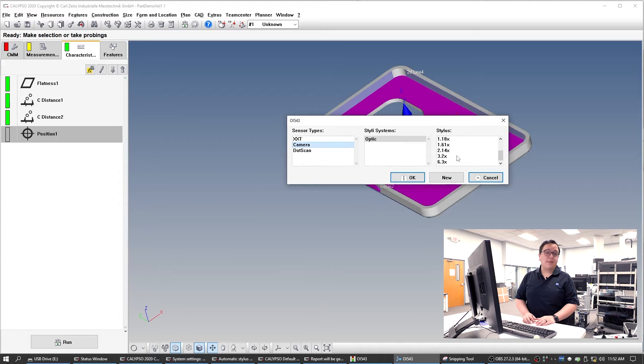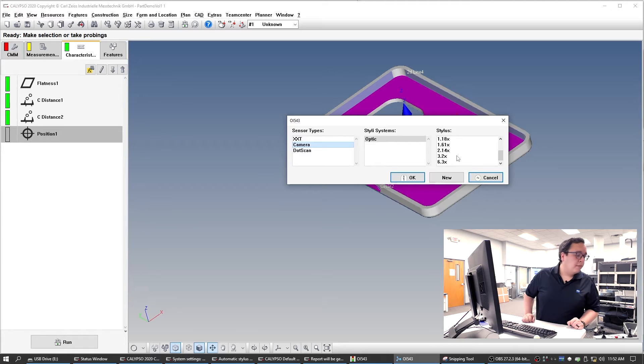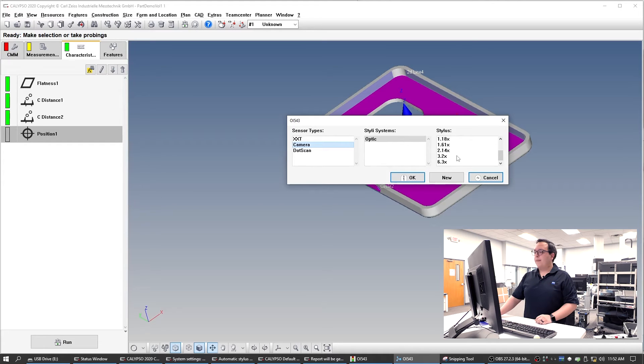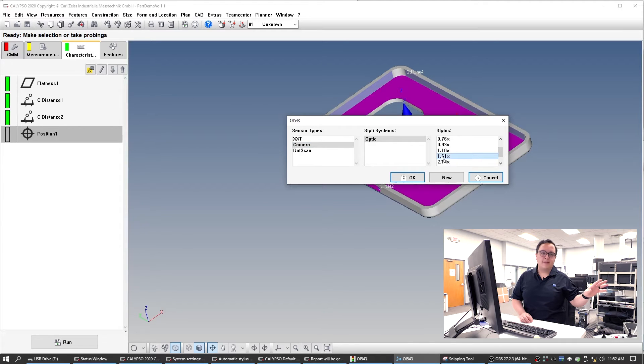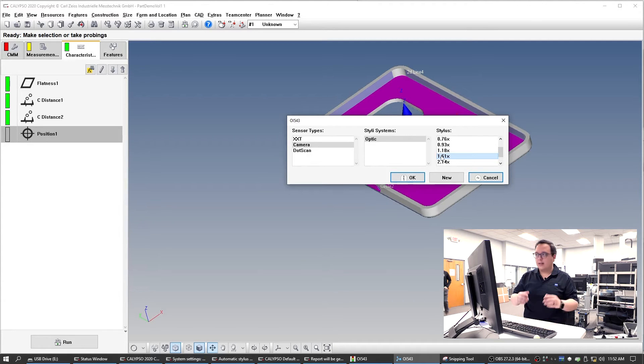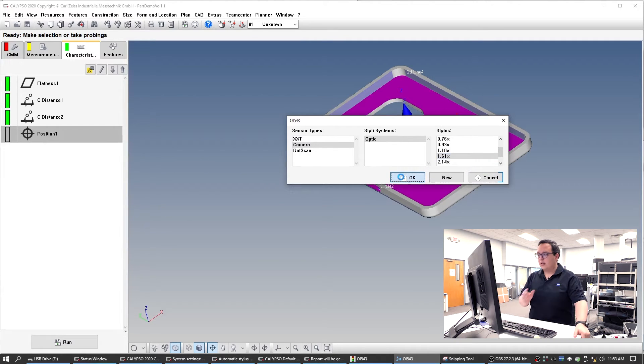We can turn on the camera by going to the little hand — this is the manual input for the stylus camera. We have ten different magnifications to pick from. Which one do we want to use? It depends on the tolerance that we're going to put on this characteristic. If it's really small, you want to measure with the largest magnification possible. If it's big tolerance, you want to make sure you can find your part. Here I will use the 161. The 161 is really special for the Oinspect — it's telecentric, so it's not going to go to a horizon. It's going to show us the whole bore as it is. Maybe we'll get into telecentricity in a later video.